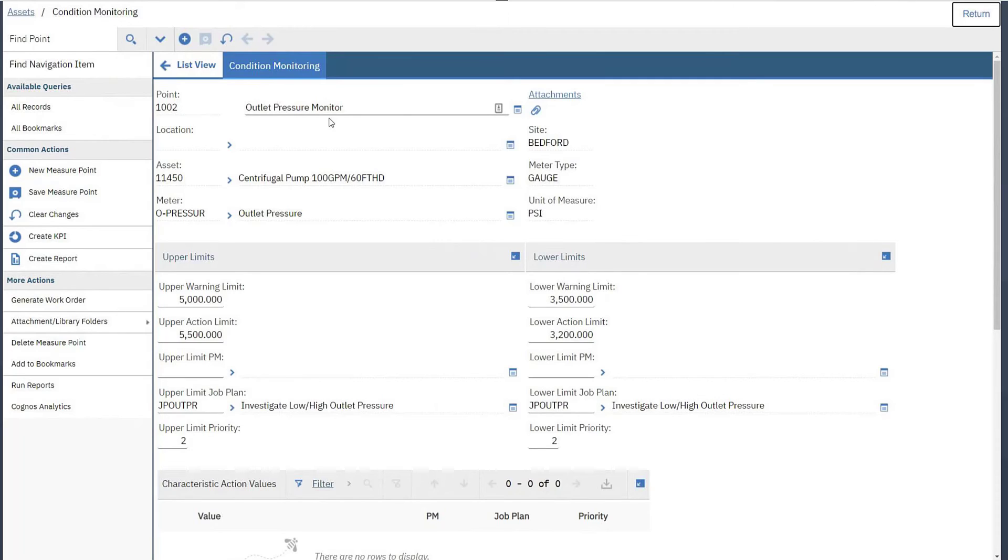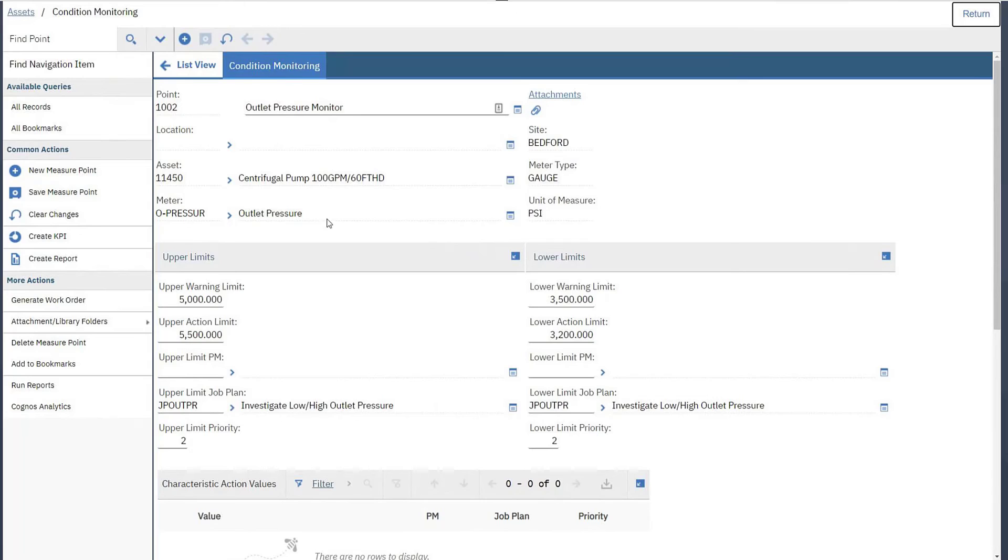You will want to determine what the range of acceptable pressure readings are for each pump and determine whether there is a band of readings that you would want to report on to an engineering group. That range can be reflected in the upper and lower warning limits. These do not trigger anything and are reportable values only.